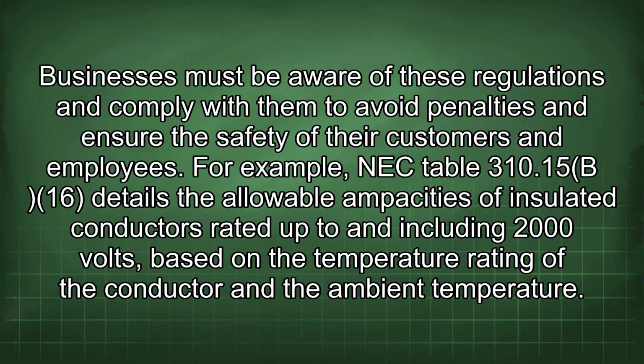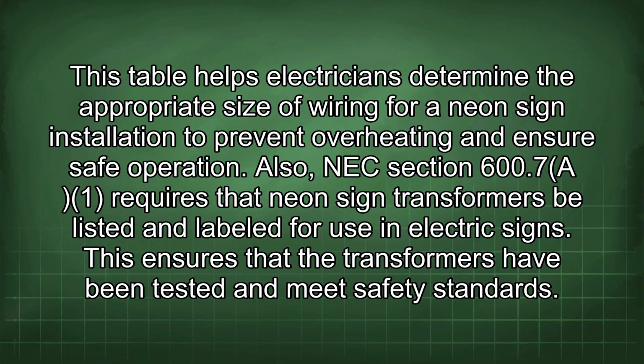310.15(B)(16) details the allowable ampacities of insulated conductors rated up to and including 2000 volts, based on the temperature rating of the conductor and the ambient temperature. This table helps electricians determine the appropriate size of wiring for a neon sign installation to prevent overheating and ensure safe operation. Also, NEC Section 600.7(A) requires that neon sign transformers be listed and labeled for use in electric signs. This ensures that the transformers have been tested and meet safety standards.